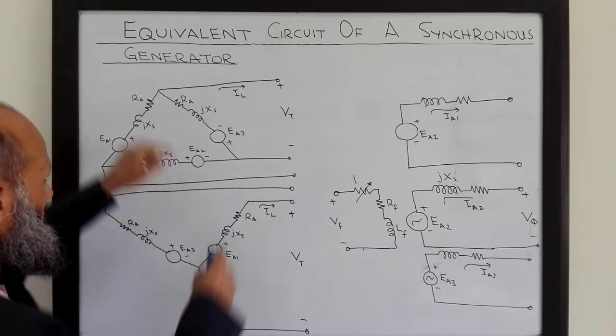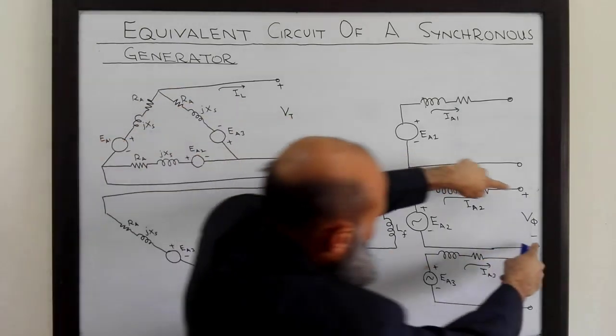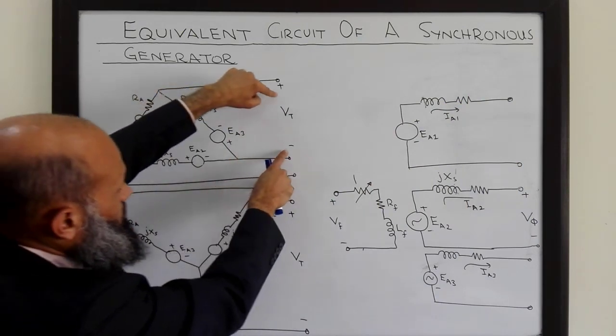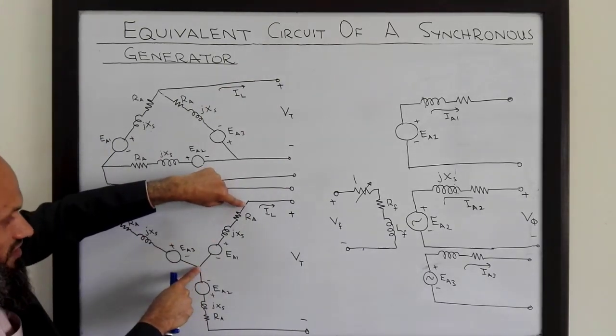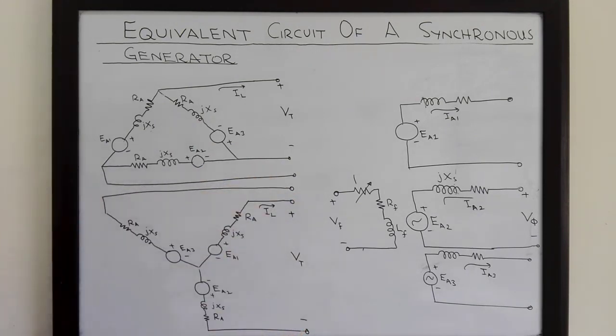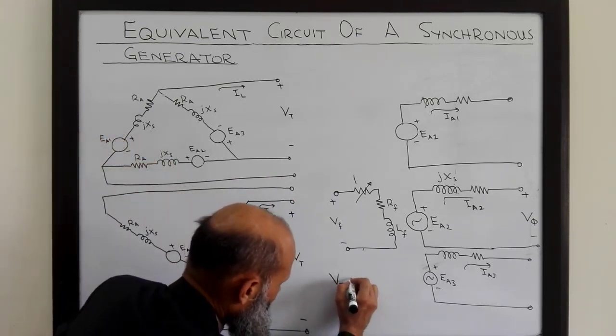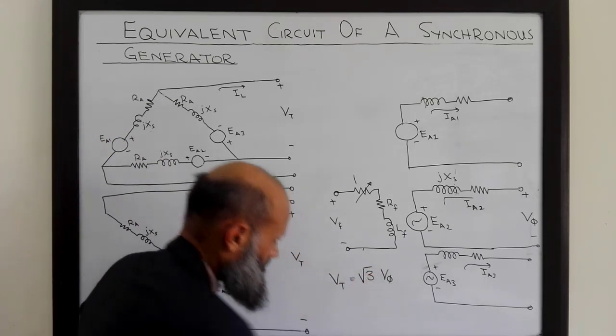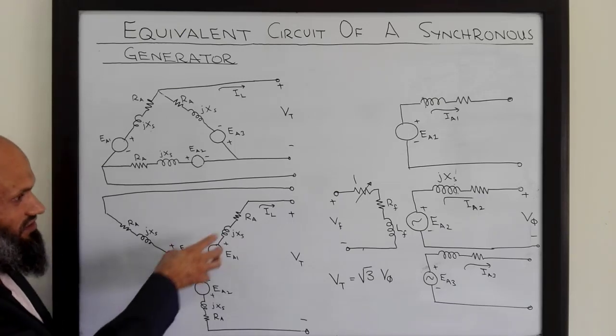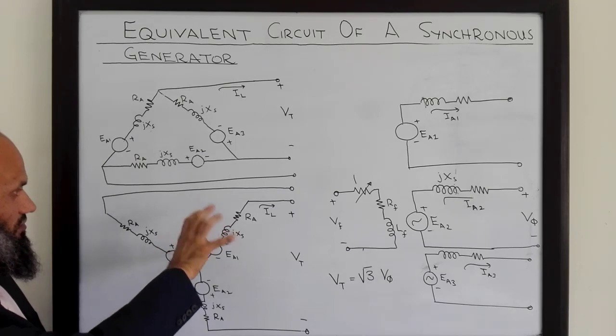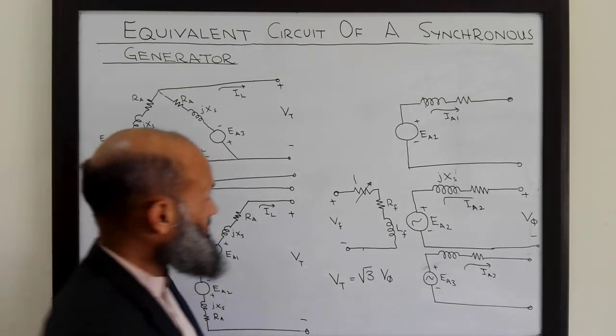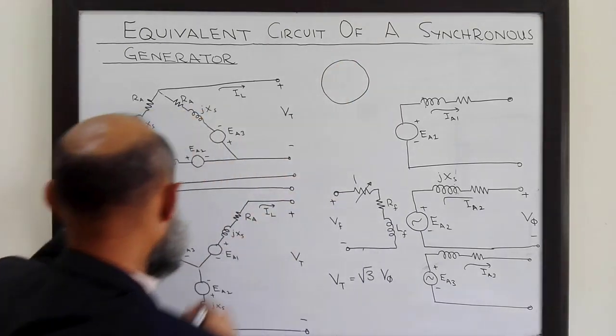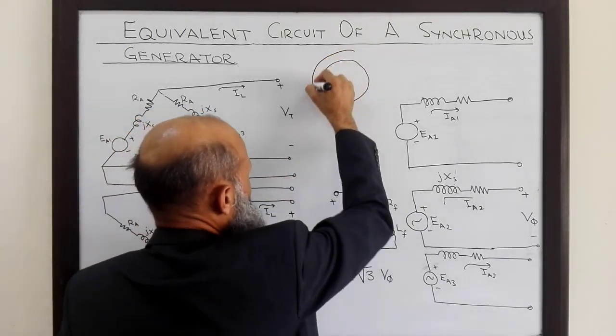In the case of delta connection, the phase voltage equals the terminal voltage. In the case of star connection, the phase voltage is not the same as the terminal voltage — the terminal voltage is square root of three times the phase voltage. Remember that these are only the electrical connections; this does not show the physical placement of coils. The coils are physically placed in the stator of the synchronous generator — rectangular coils with multiple turns, with each side of the coil placed in slots in the stator.